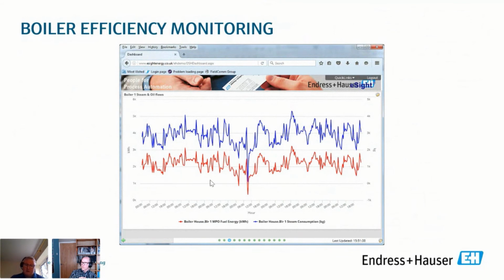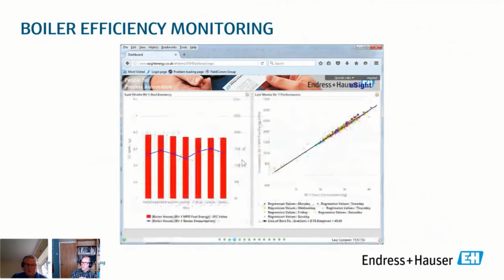You can use exactly that same data and just graph it up differently. So here's the same data we've just seen, but instead these bars now show the fuel economy of the boiler, because they're the kilowatt hours of fuel per kilogram of steam generated. Each bar tells me what the fuel economy is. This is a very useful benchmark, because I can see straight away if anything creeps much above 0.8, say, then I know there could be a problem.